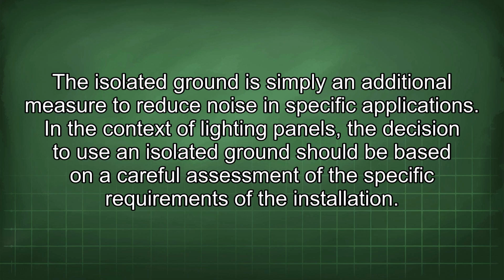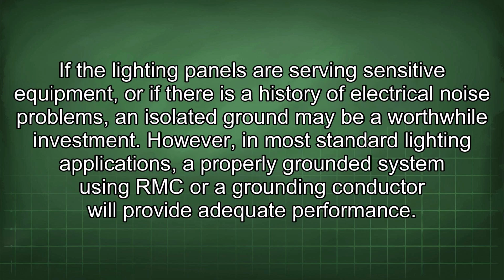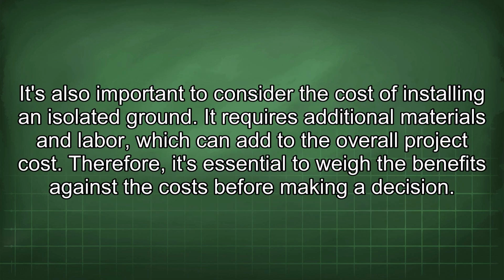In the context of lighting panels, the decision to use an isolated ground should be based on a careful assessment of the specific requirements of the installation. If the lighting panels are serving sensitive equipment, or if there is a history of electrical noise problems, an isolated ground may be a worthwhile investment. However, in most standard lighting applications, a properly grounded system using RMC or grounding conductor will provide adequate performance. It's also important to consider the cost of installing an isolated ground. It requires additional materials and labor, which can add to the overall project cost. Therefore, it's essential to weigh the benefits against the cost before making a decision.